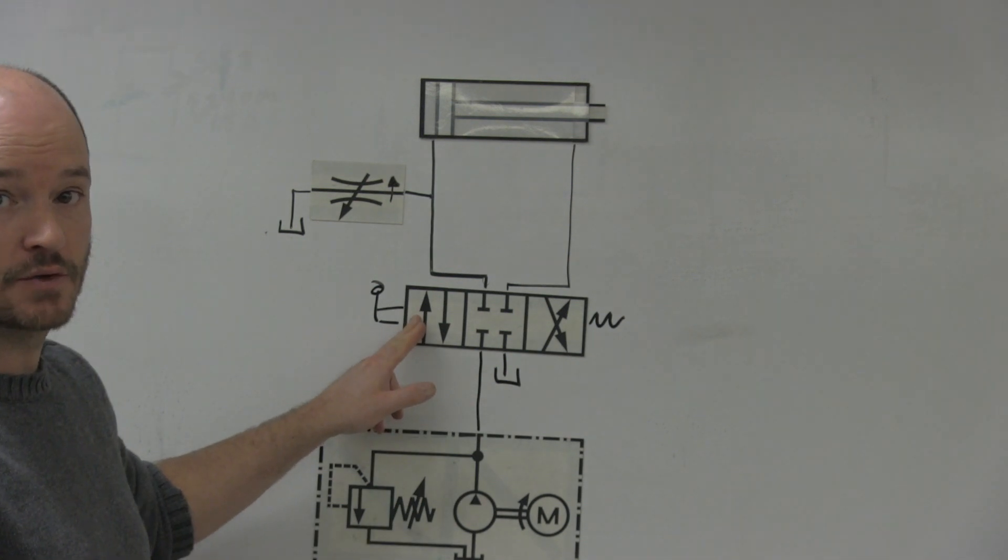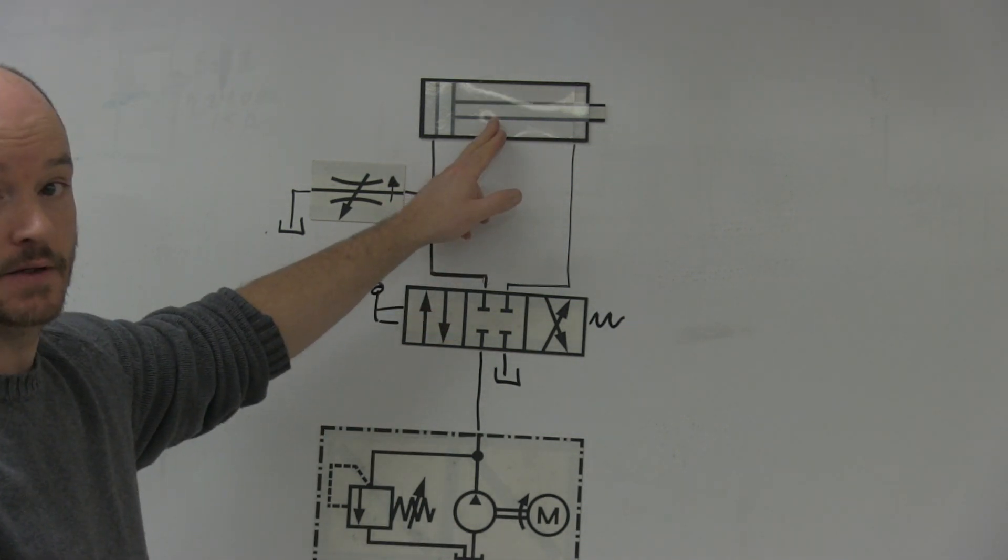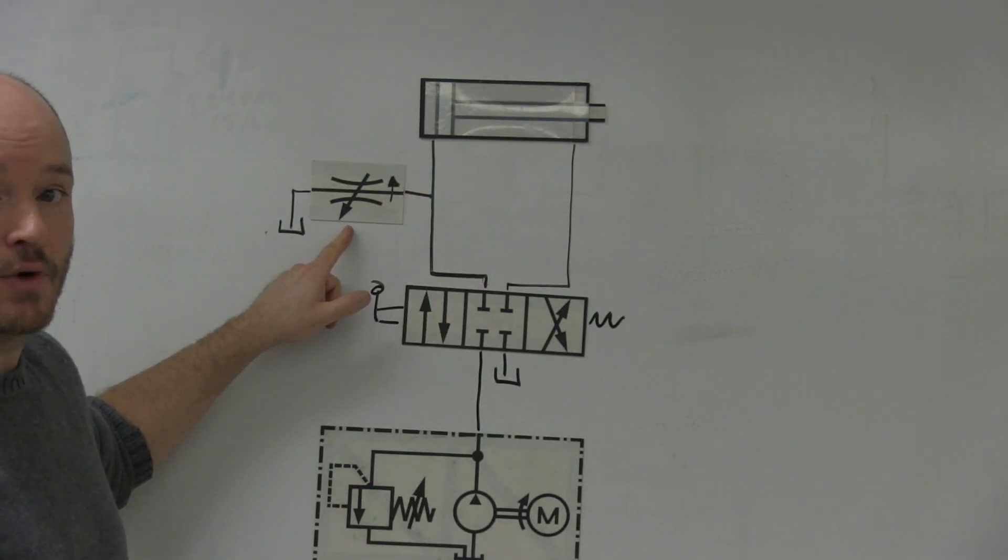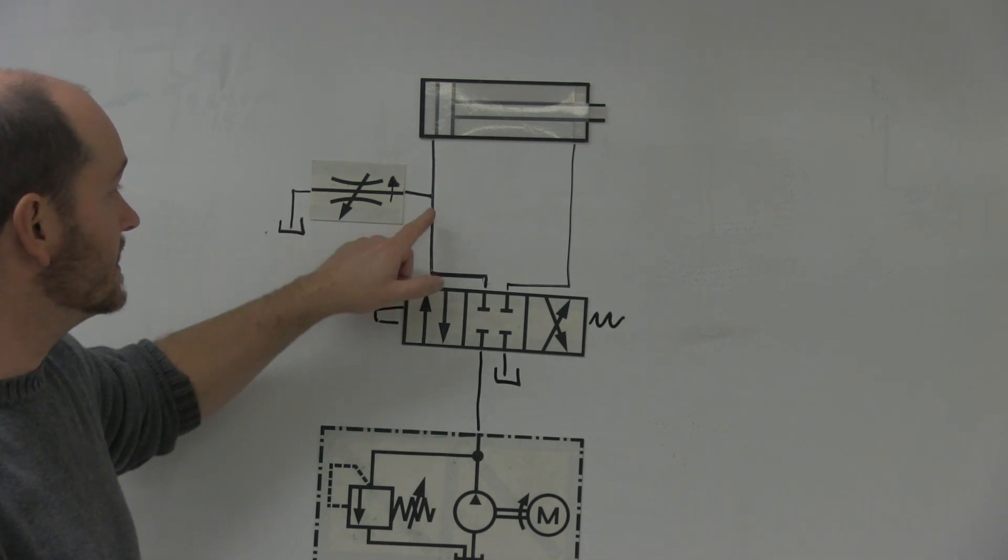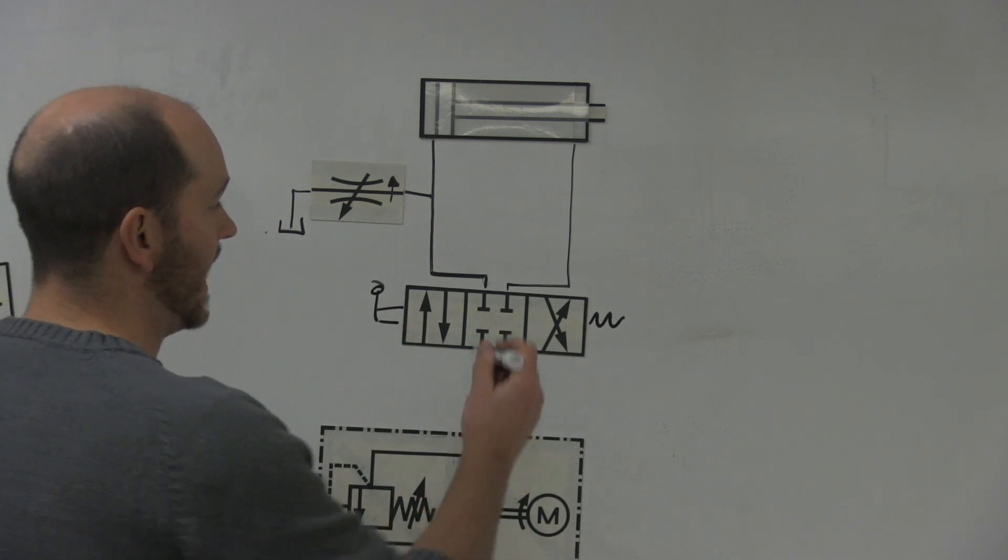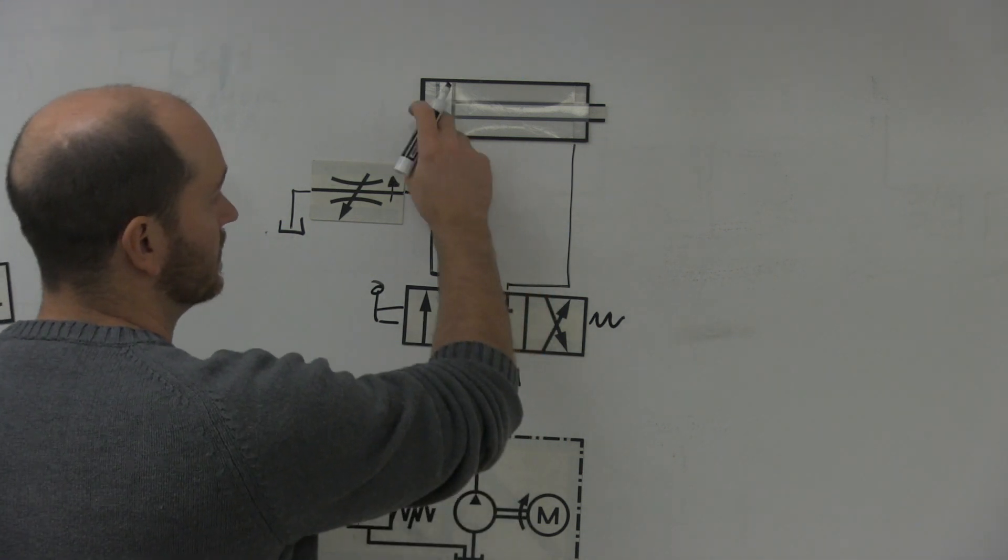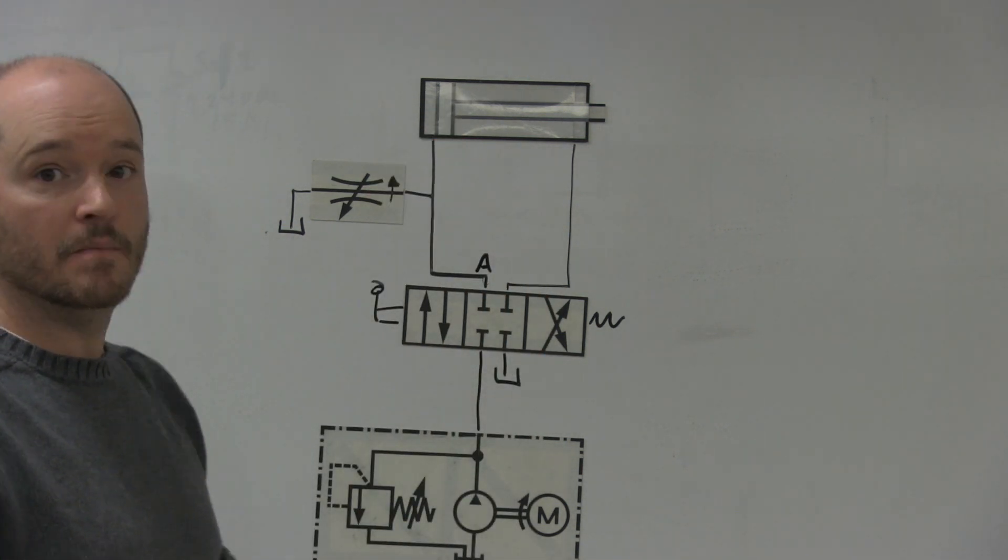Here I have a four-three directional control valve controlling a double acting cylinder. And here I have a pressure compensated flow control, or a pressure compensated needle valve. Depending on who you're reading, they can use both terms. It's going down to tank, which is teed off of my A line right here going to the blind end of my cylinder.